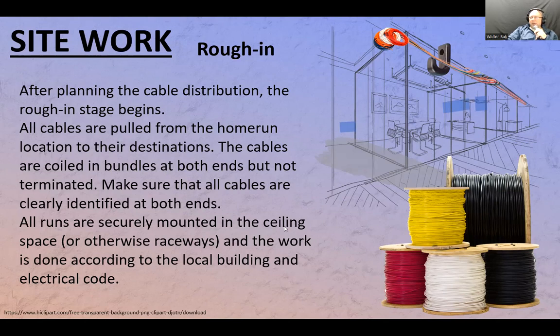For the most part, if it's data, you're just going to be dealing with the type of insulation that's being used. If it is electrical wires, again, same thing, right? Some of the wires you can run surface mount exposed, like NMD90 can be mounted exposed, as long as it's done a certain way. You can't mount it directly on metal surfaces. It has to be on timber, wood, and things like that. And the way things have to be suspended, like for example, data wires. Let's not get ahead of ourselves here.